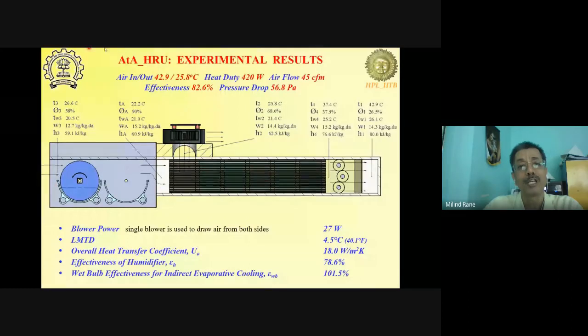Another thing which I would like to call your attention to is the air-to-air heat recovery units. These are plastic air-to-air heat recovery units. Recently, just last month, our patent on this got granted. In this case, we have a plastic air-to-air heat recovery with air temperature coming in from outdoor at about 42.9 degrees with a low RH. Typically, most of the high ambient weathers have low RH at that time. And then this air was cooled and delivered at 25.8 degrees centigrade.